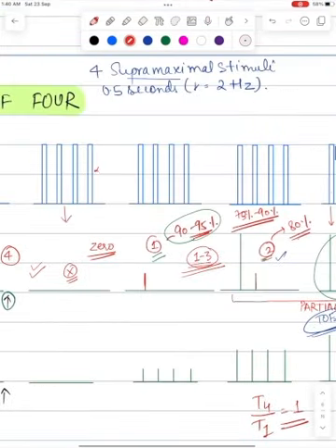In such situations, you will have to make use of post-tetanic count, which we will discuss in a short while. Also, when used continuously, an interval of at least 10 seconds should be allowed between each set of TOF stimulation. 10 to 12 seconds should be given before each set of TOF stimuli.